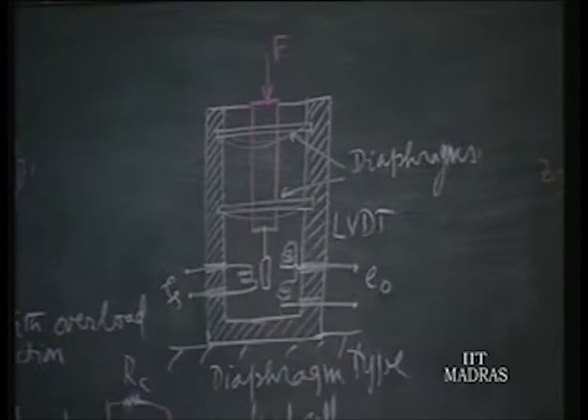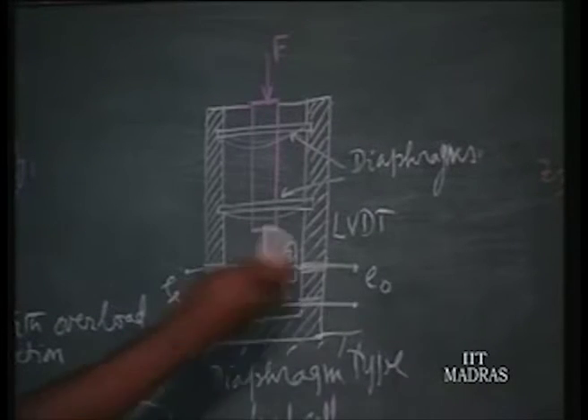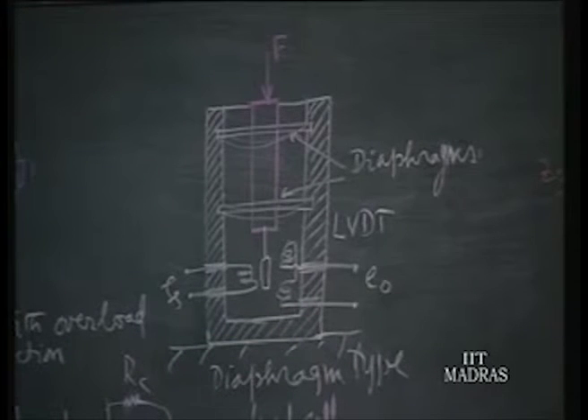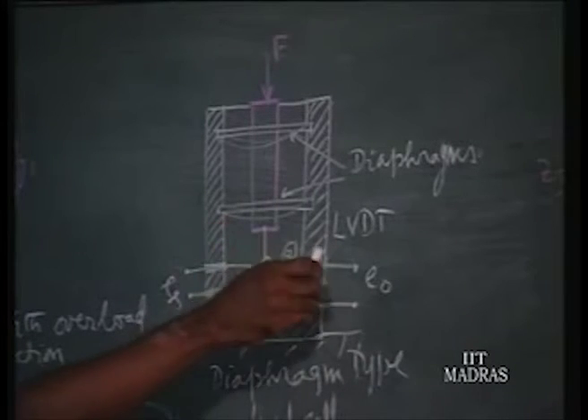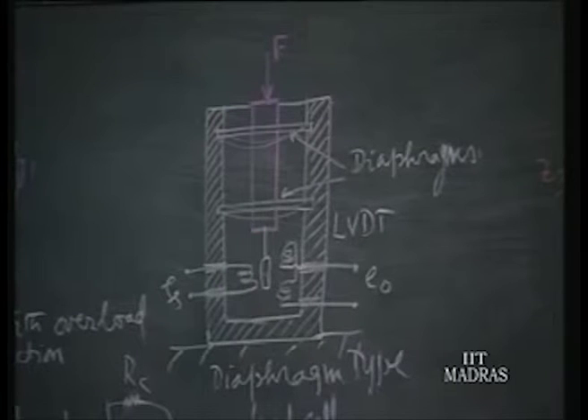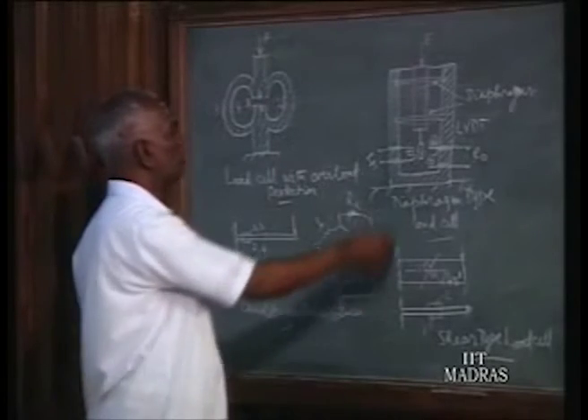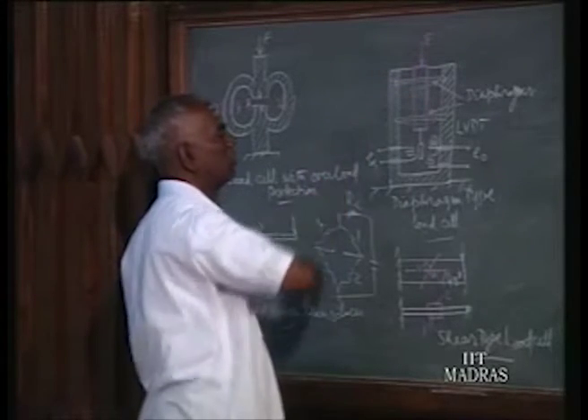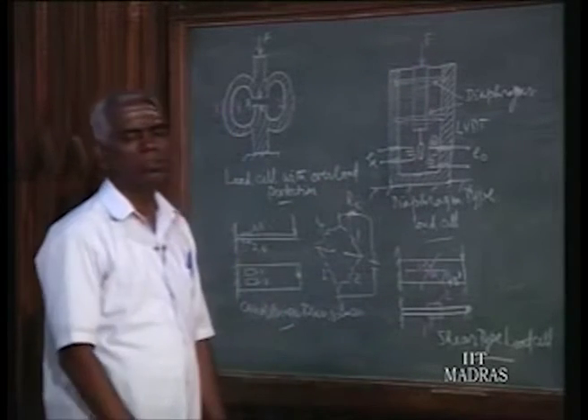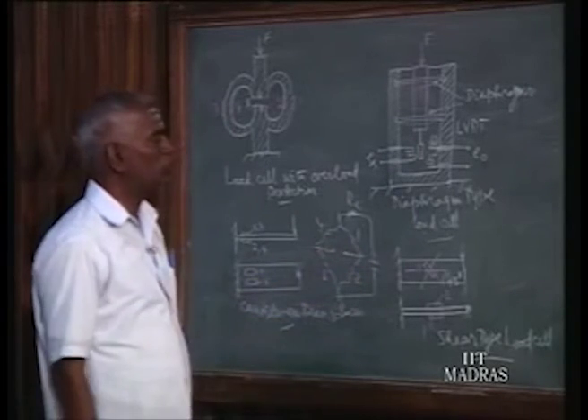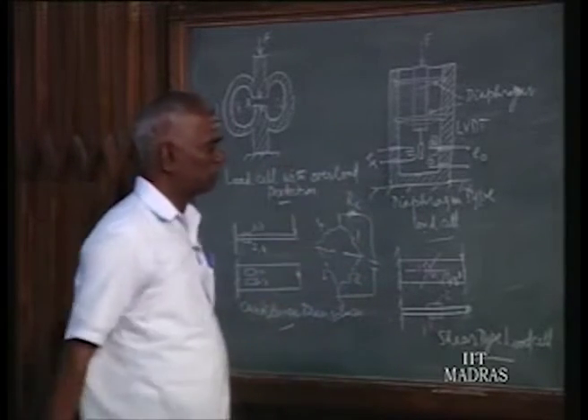And further we process it as we learnt earlier in LVDT, with or without amplification, by giving it to a phase sensitive demodulator and low pass filter, and finally we get a displacement. That displacement is written in terms of Newton or kilogram force. That is how the displacement reading is calibrated in terms of force unit. So here we have two transducers, one to transduce the force into deformation and this deformation back to voltage. That voltage is written in terms of Newton. So two transducers in essence.